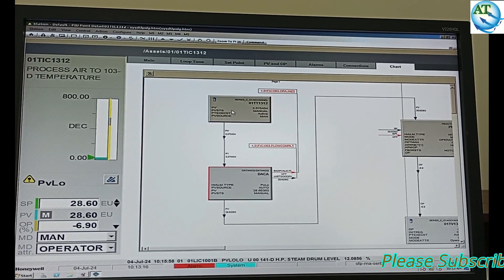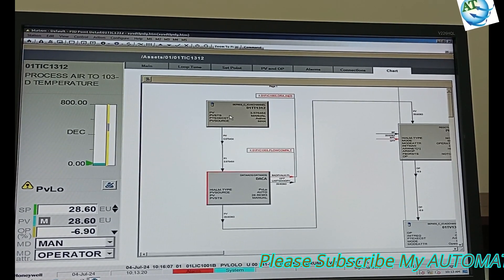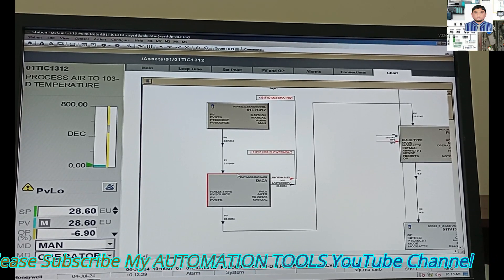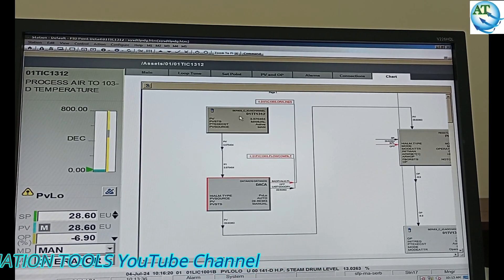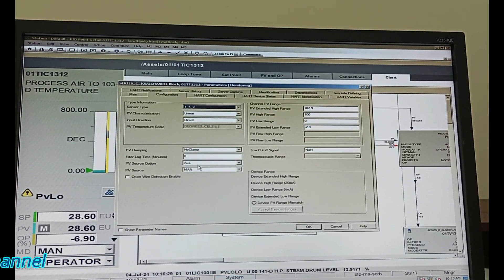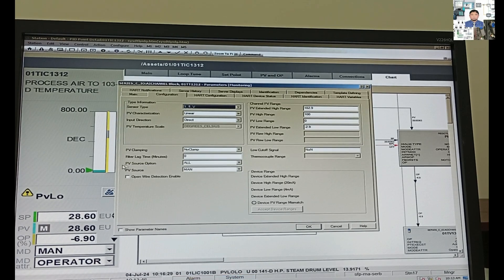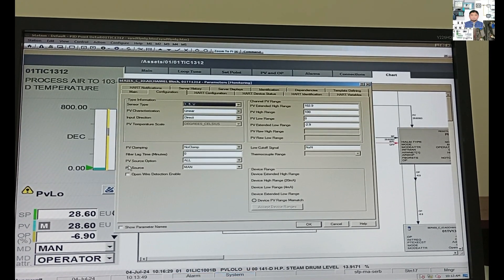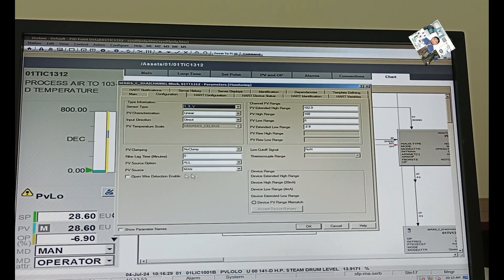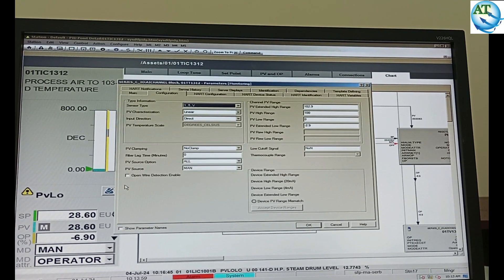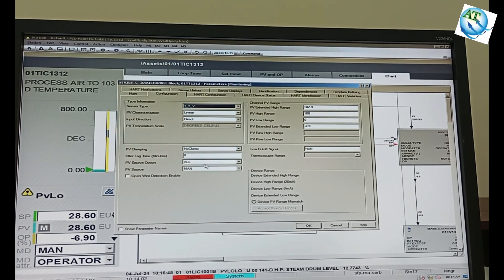This is how we force the analog input module in the logic system without hampering the process. You can change the field instrument or field transmitter using this process. After finishing the job — the replacement or maintenance — you go back to the block, go to configuration mode, and here you can see the PV source option. We have changed the only-auto to all and selected PV source to man.